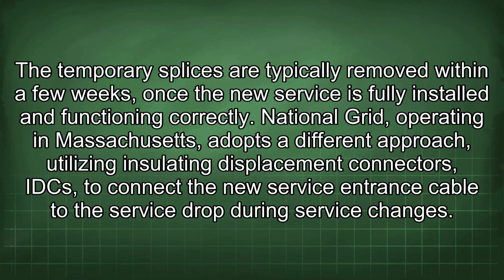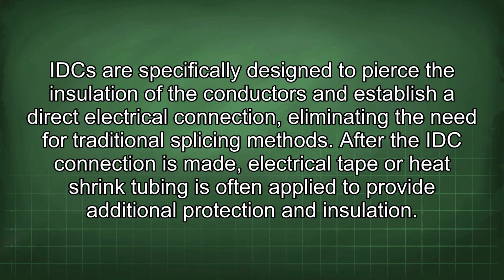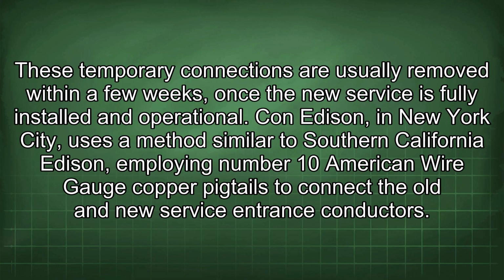National Grid, operating in Massachusetts, adopts a different approach, utilizing insulation displacement connectors (IDCs) to connect the new service entrance cable to the service drop during service changes. IDCs are specifically designed to pierce the insulation of the conductors and establish a direct electrical connection, eliminating the need for traditional splicing methods. After the IDC connection is made, electrical tape or heat shrink tubing is often applied to provide additional protection and insulation. These temporary connections are usually removed within a few weeks once the new service is fully installed and operational.